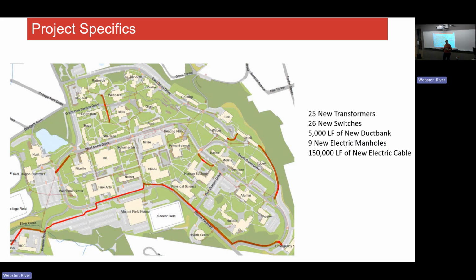And we have to keep the power on to each building, right? So the primary electric here is being replaced. It includes replacing the transformers, and now they're going to be replaced with something called a dual tap transformer—I'll get into that a little bit. Right now everything's operating at 4,800 volts. With the future electrification and the future demand, we're going to need to have 15 kV. The existing transformers are near the end of their useful life, so when we replace them, we're setting ourselves up for the future so they can operate at the current voltage or at the future voltage.